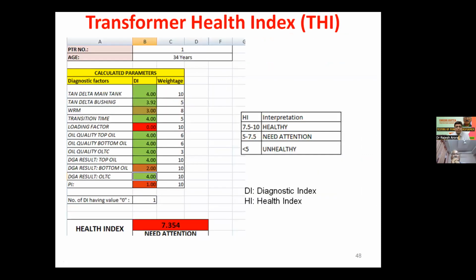So from there arises the concept of transformer health index. Basically, what we are doing here is empirically collecting all the results and evaluating them based on whether they are good or not. We are bringing all the essential results like tan delta, winding resistance, the transition time of the OLTCs, the quality of oil, its DGA, PI values, under one window, and we are giving it a diagnostic index.